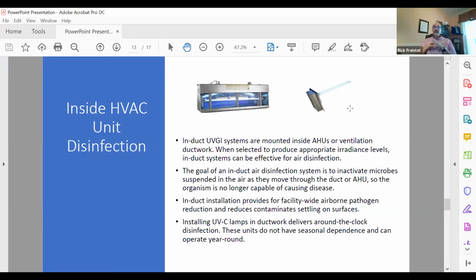In-duct installations provide facility-wide airborne pathogen reduction and reduce contaminants settling on surfaces if you're killing them in the air. Installing UVC lamps in ductwork delivers around-the-clock disinfection. The units have no seasonal dependence and can operate year-round, though they use a lot of energy. Since they're UVC and up in the ductwork, people in rooms aren't exposed to them, and they can be effective as well.